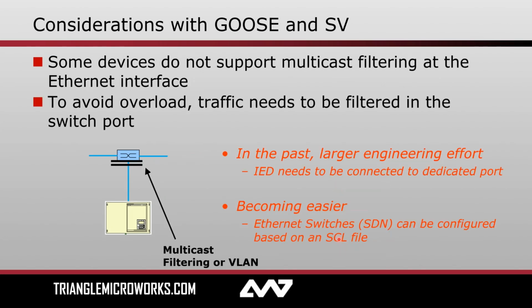So here's another way of accomplishing the same thing, but using the filtering at the Ethernet switch. In this case, you could use either VLANs or MAC address filtering depending on the capabilities of your given switch. And you might do this, for example, if your particular IED does not support MAC address filtering. There are a couple of downsides to this. I would still say it's quite popular and widely used, but there are just a couple of things to keep in mind.